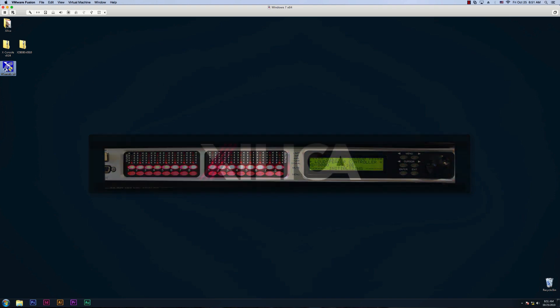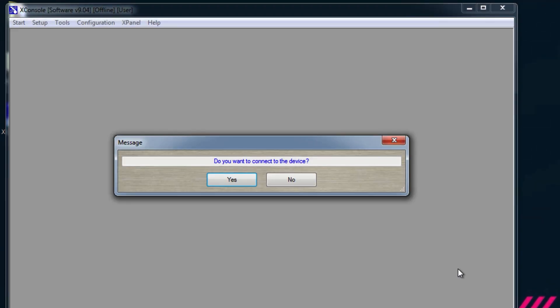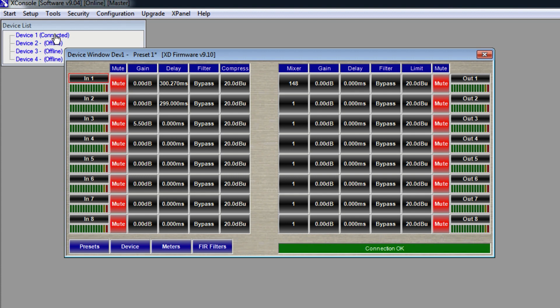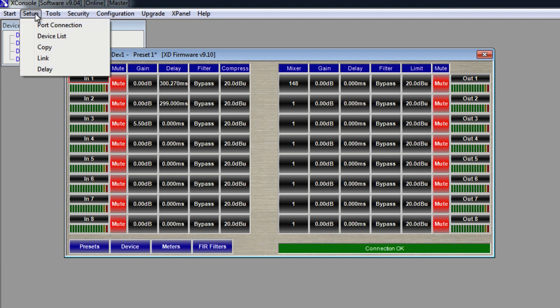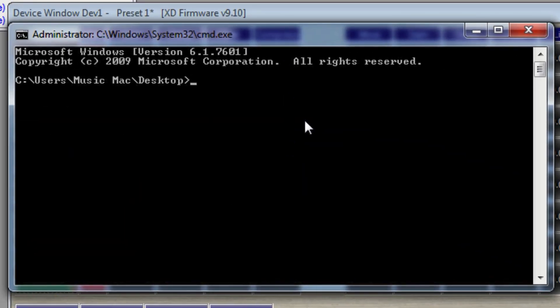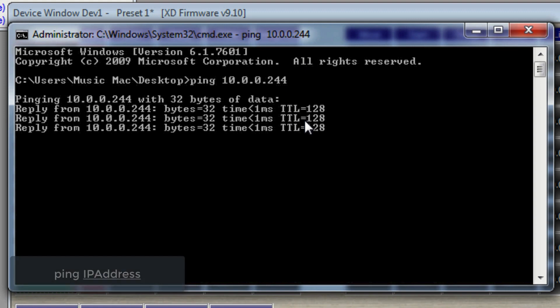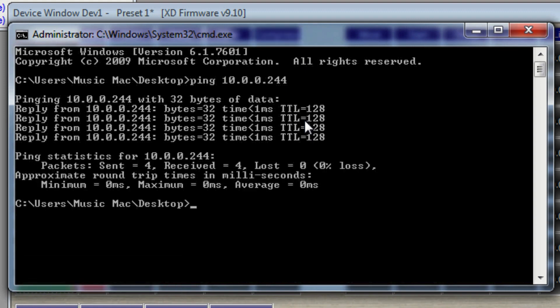Once it's booted up, open up X-Console. Click Yes to connect to the device. You should see your device as connected. If you're having trouble connecting, please try pinging your device. To do this, go up to Setup, Port Connection, and go into the command prompt. Type ping and the IP address of your device. In my example, I'm going to type ping 10.0.0.244. If you have information that populates, that means you have a good connection. If you see no information or request timeout, please try a different cable or connecting using USB or RS-232.